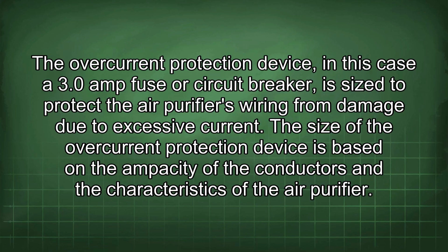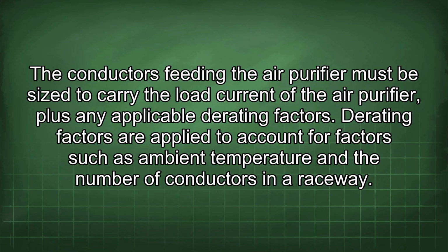The size of the overcurrent protection device is based on the ampacity of the conductors and the characteristics of the air purifier. The conductors feeding the air purifier must be sized to carry the load current of the air purifier, plus any applicable derating factors. Derating factors are applied to account for factors such as ambient temperature and the number of conductors in a raceway.